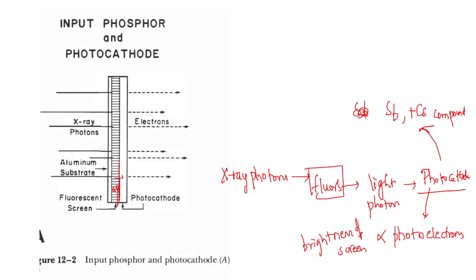The photocathode is directly applied to the CsI input phosphor, so light from the CsI directly passes into the photocathode. In the past, there used to be a transparent barrier between the fluorescent screen and the photocathode, but now there is no transparent barrier — there is direct passage of light from the fluorescent screen to the photocathode.